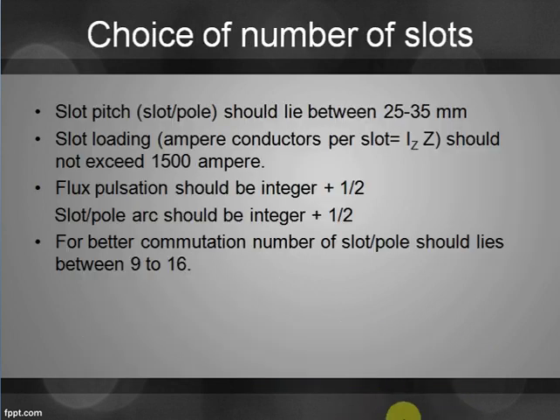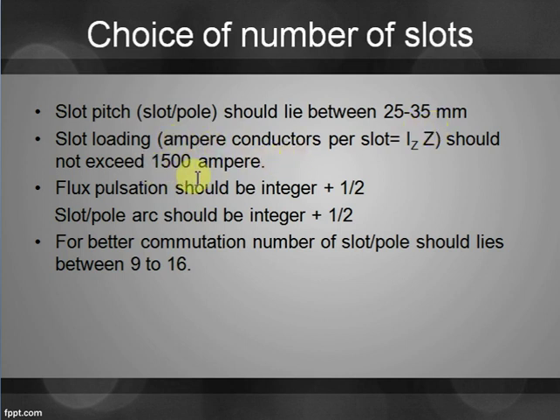Choice of Number of Slots: Slot Pitch should lie between 25–35 mm. Slot Loading should not exceed 1500A. Flux Pulsation should be an integer plus half. Slot per Pole Arc should be an integer plus half for better commutation.